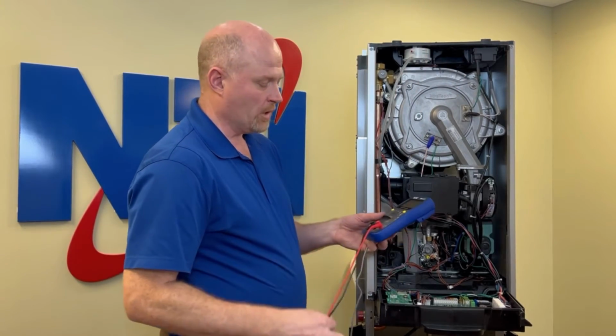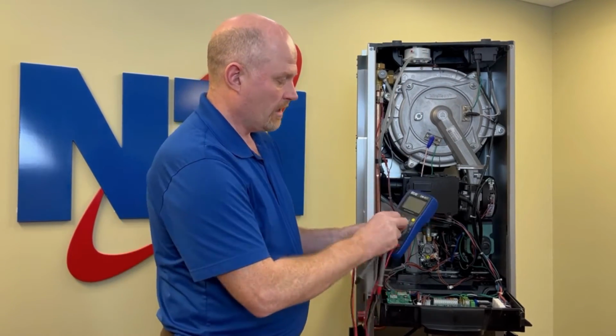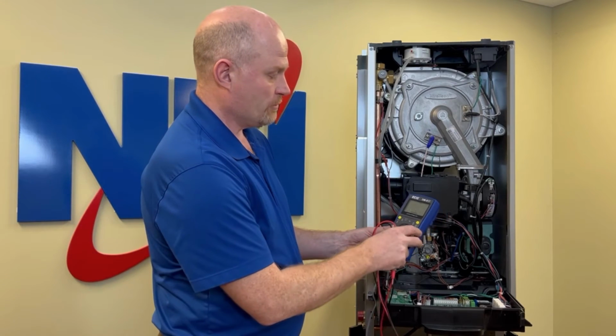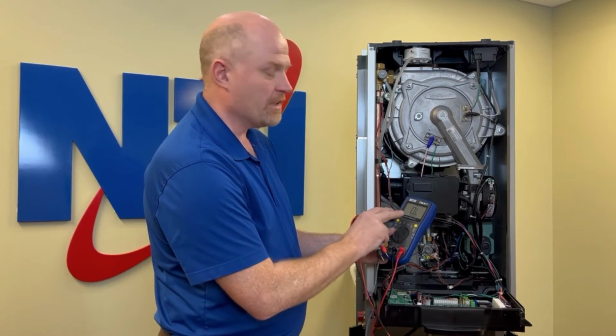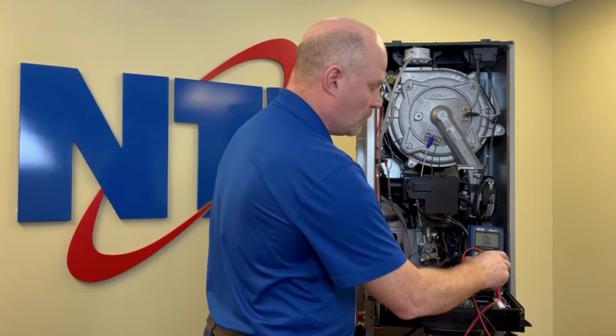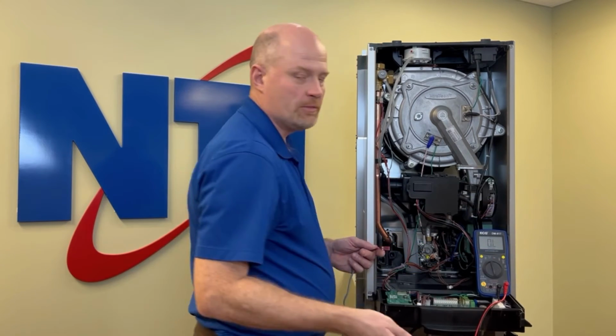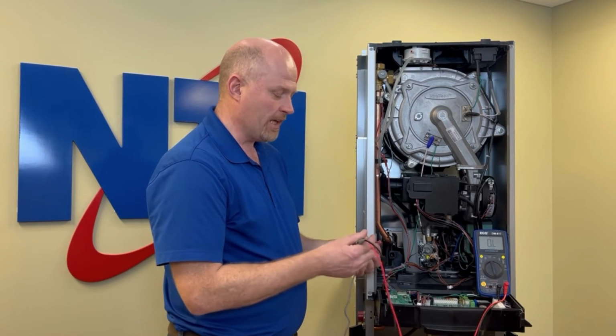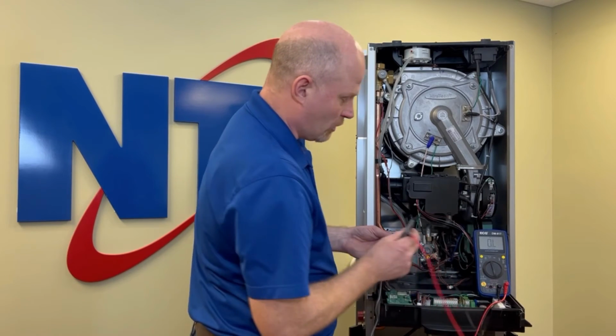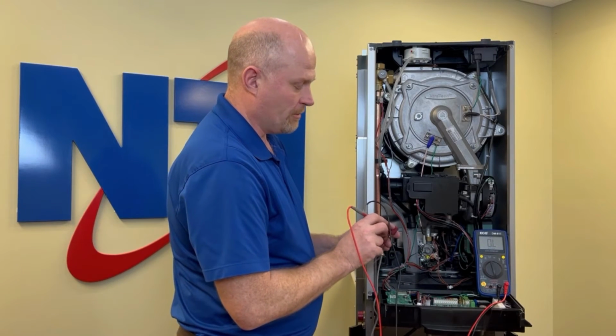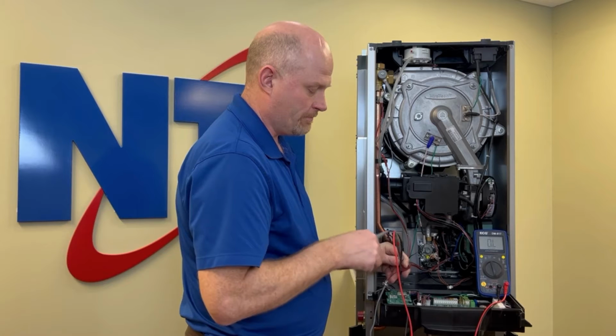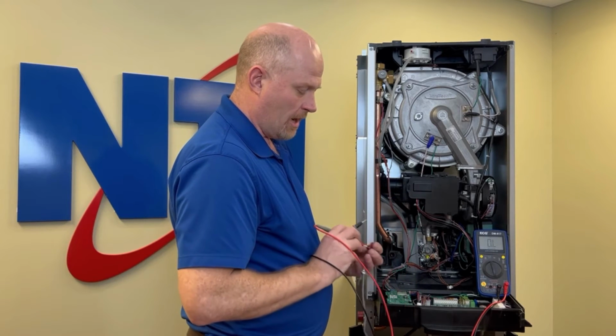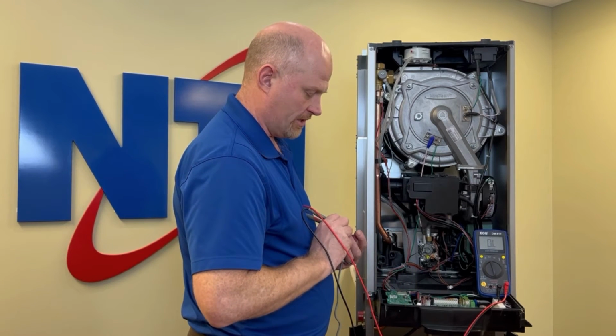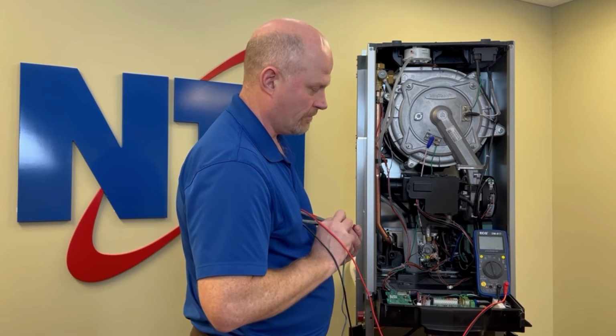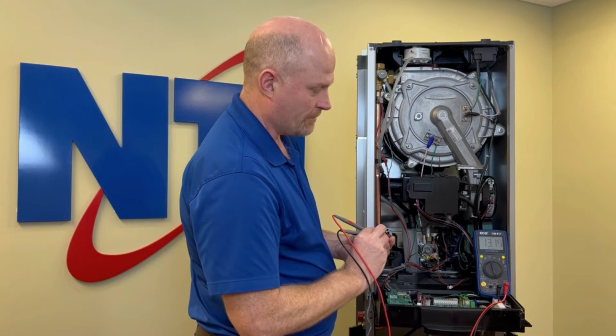To do that, you'll want to grab your voltmeter, set it to the ohms range. Now, if your meter is not auto ranging, you'll want to set it to a fairly high number, 200,000 ohms, something in that region. This one is auto ranging, so it automatically defaults to mega ohms until it sees something different. And we're going to measure resistance across these two screw terminals and see what we get.